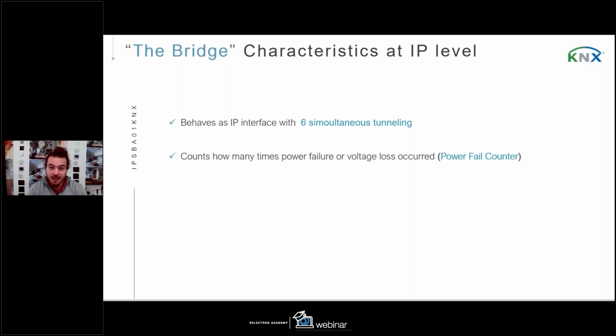Some information about the IP world. We have the opportunity to enable up to 6 simultaneous connections over IP, which means that we can enable 6 tunneling connections to the device, point to point. We can calculate and count how many power failures we had on the KNX bus. It can be very useful for maintenance purposes, because we can understand if the system had a power failure even without a logger. We can monitor the actual voltage and actual current consumption of the bridge, so we can understand if we have already reached the maximum consumption that we can supply with this power supply.